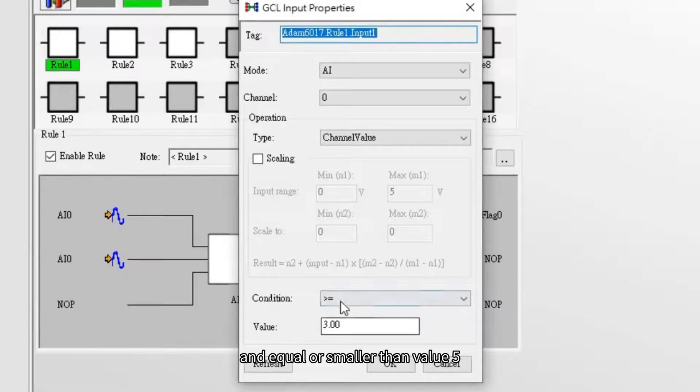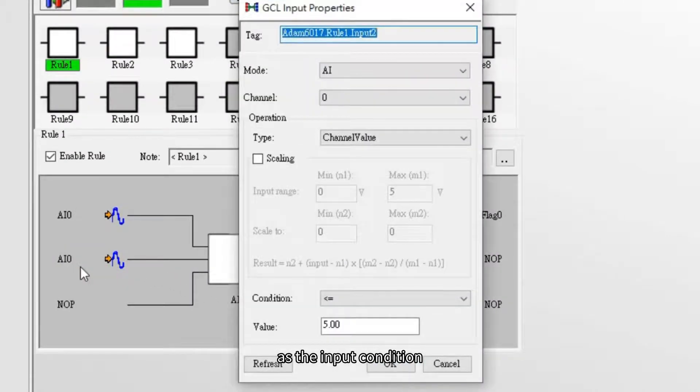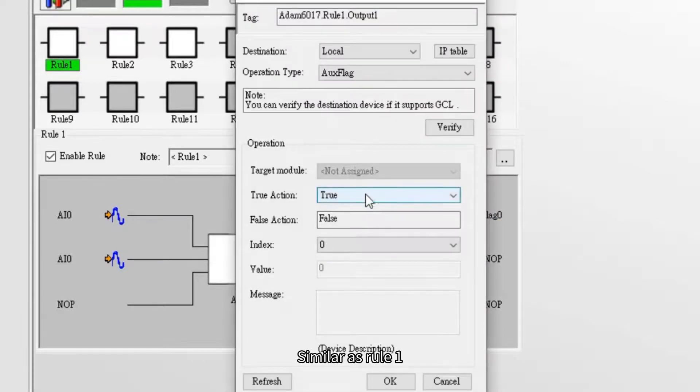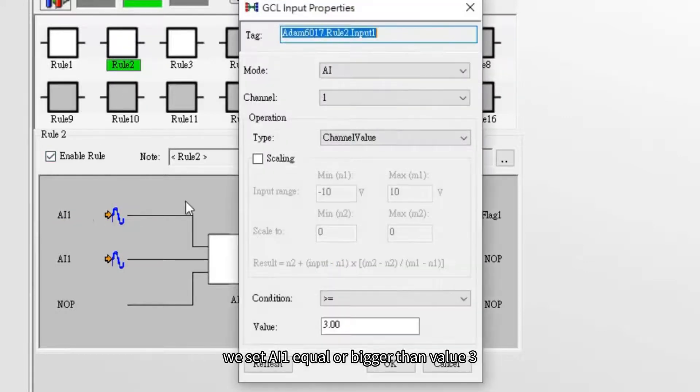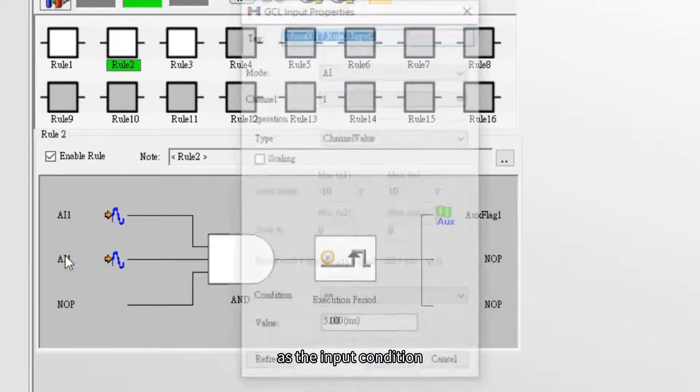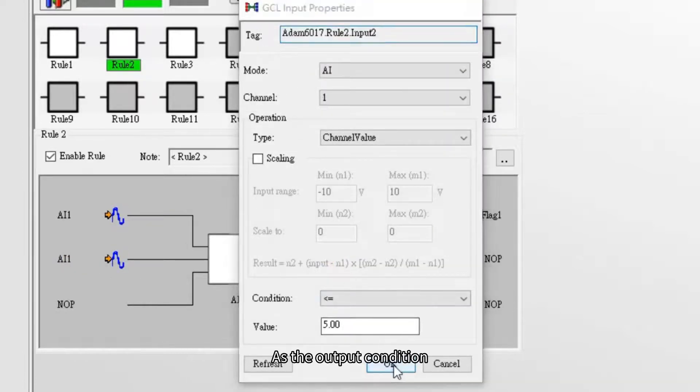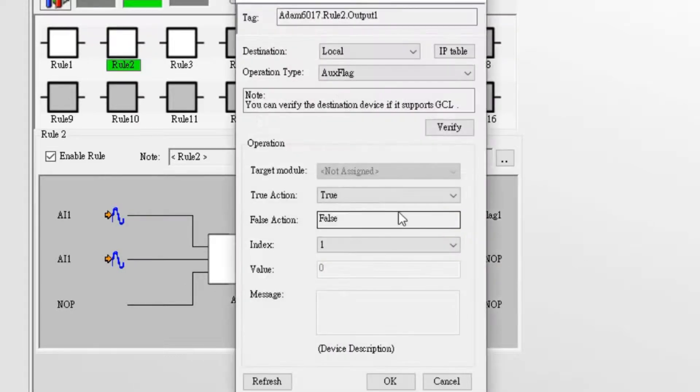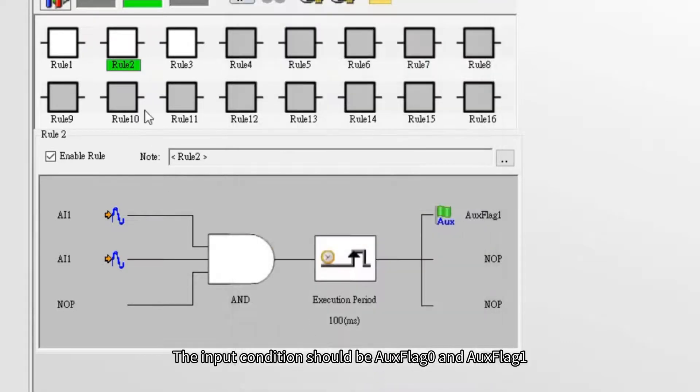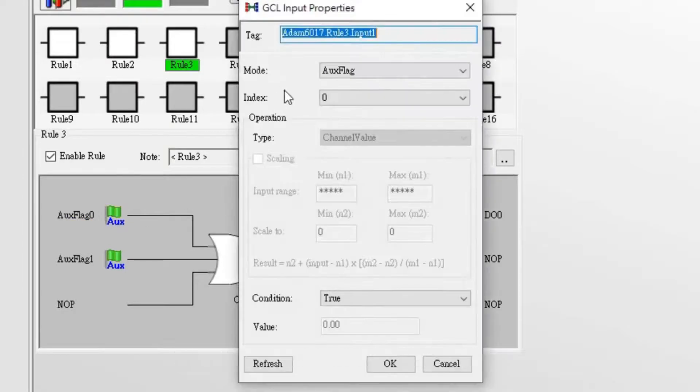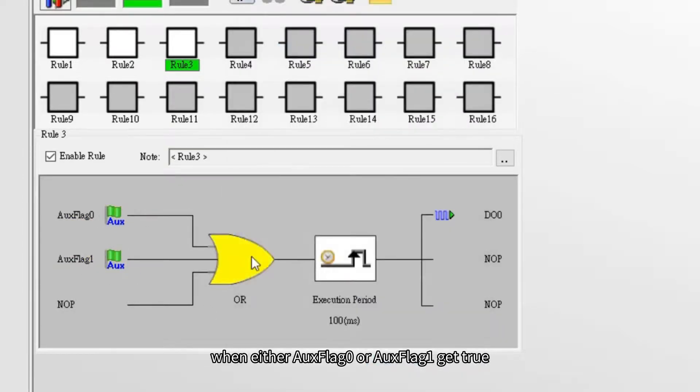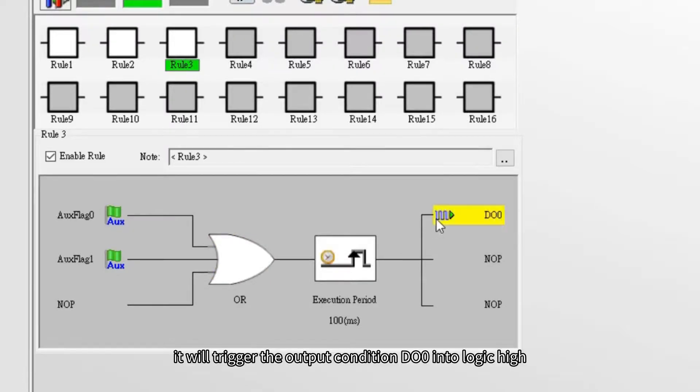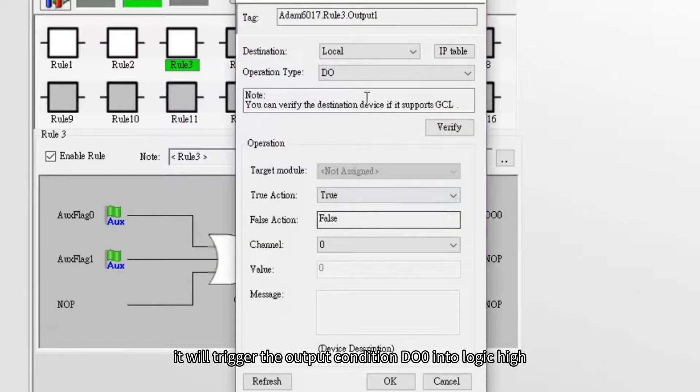Here is the GCL rule to set in utility. Both rules are set in local input module, which is ADAM 6017 here. In the rule 1, set AI0 equal or bigger than value 3 and equal or smaller than value 5 as the input condition. As the rule 2, similar as rule 1, we set AI1 equal or bigger than value 3 and equal or smaller than value 5 as the input condition. As the output condition, we set the Aux flag 1 as true. In the rule 3, the input condition should be Aux flag 0 and Aux flag 1. When either Aux flag 0 or Aux flag 1 gets true, it will trigger the output condition DO0 into logic high.